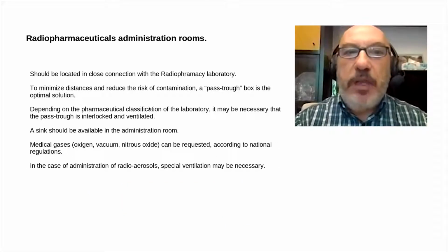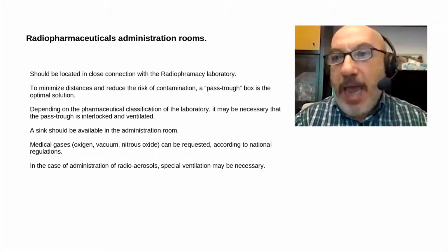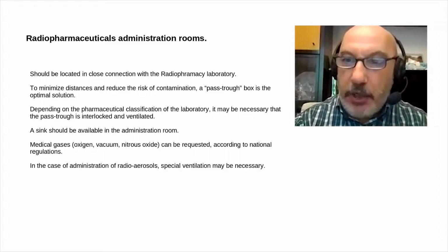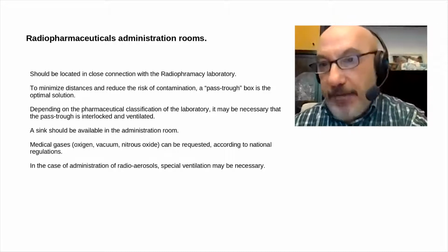After the reception, the patient is sent to an administration room. The administration room ideally should be in close connection with the radiopharmacy, but should not be inside the radiopharmacy. First of all, we should have a separation between a laboratory area and an area for patients.